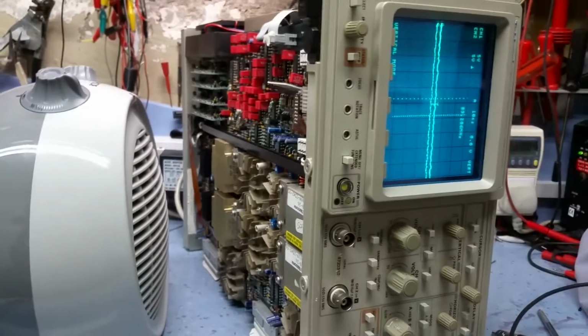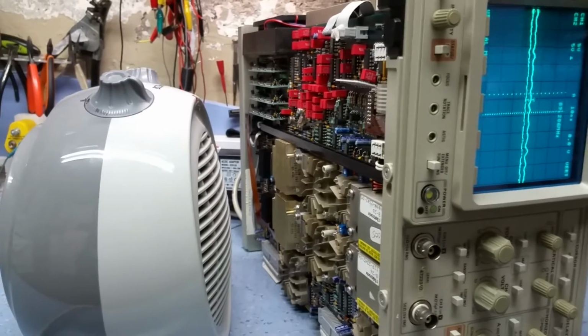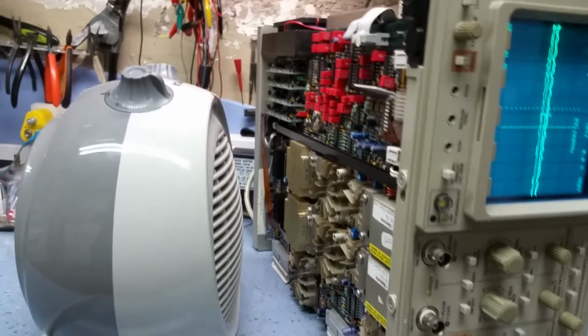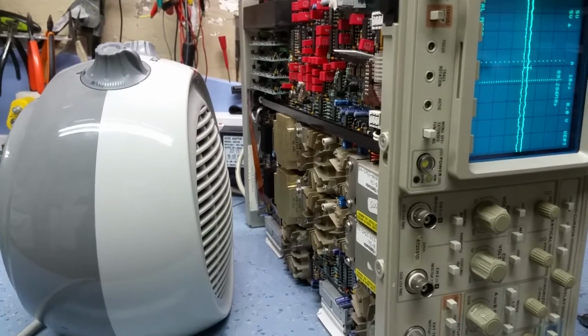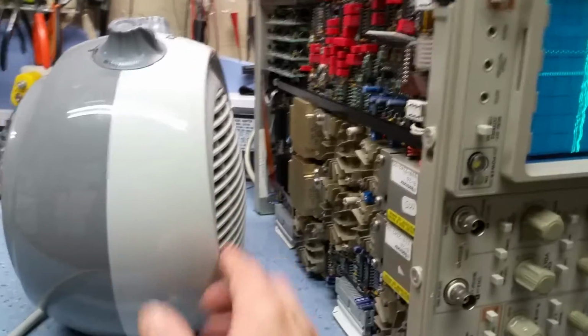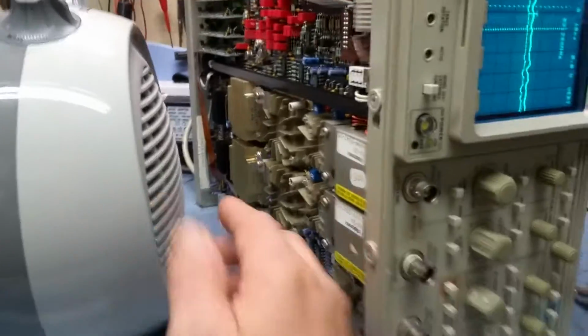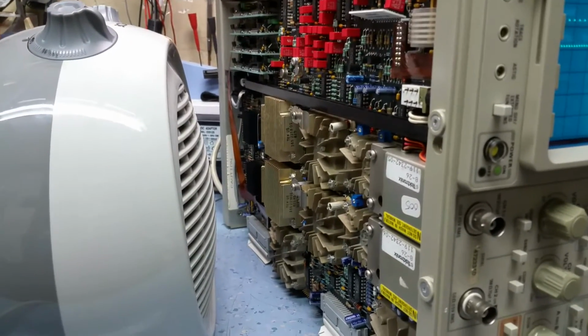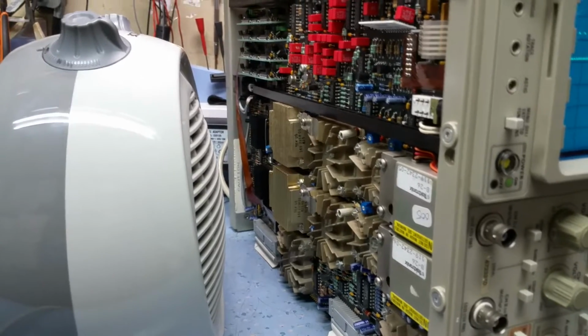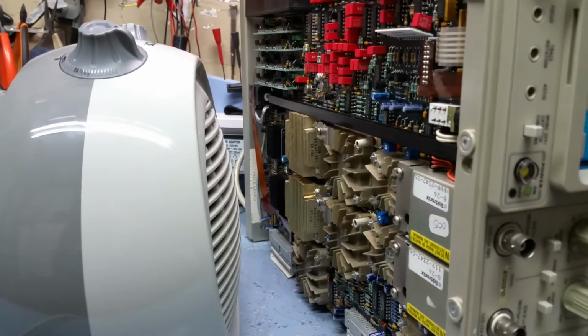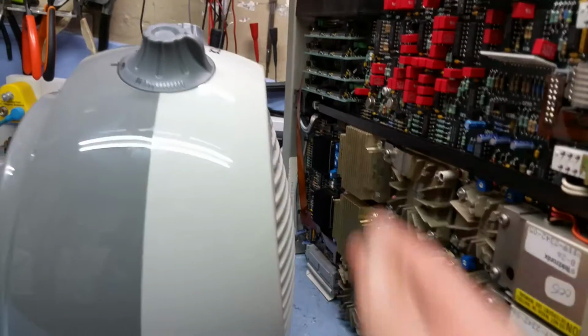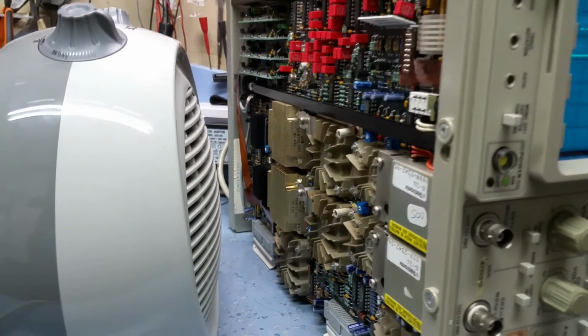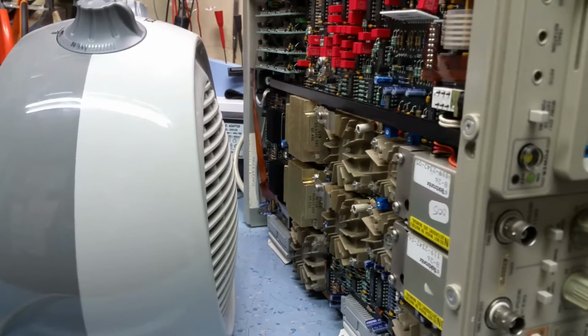Also, it's worth bearing in mind these 2440 scopes, and all of the range of the Tektronix scopes, you can't run them without forced air from this fan onto these hybrids. I mistakenly connected a Vent-Axia fan up on the bench and went inside, and the fan had fallen off the bench. When I got back, these chips were probably 70-80 degrees C. I'm going to shorten their life pretty quickly like that.